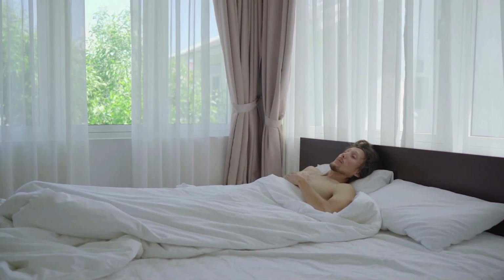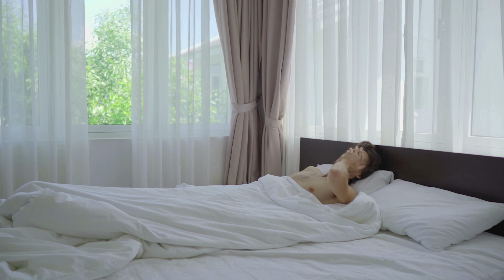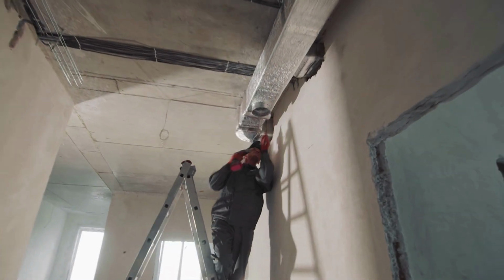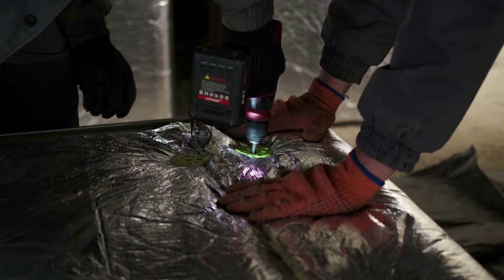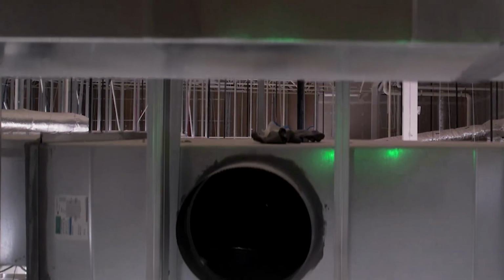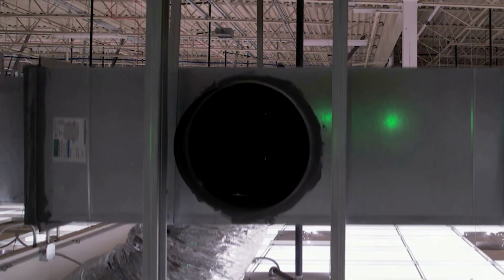A lot of times people complain they have lack of airflow to bedrooms, and usually it's because the ductwork isn't sized correctly. So the return is one of the big things we'll change to make sure it's properly sized to the right unit, based off the load calc given at the time of inspection.